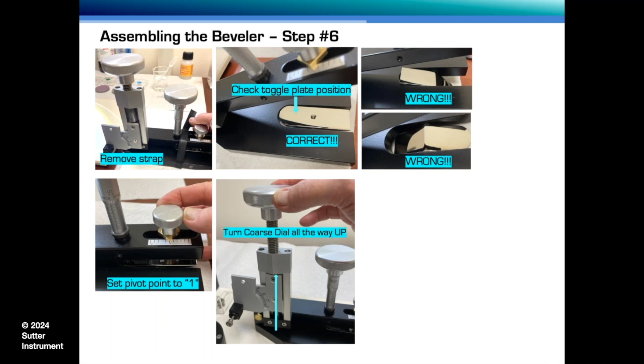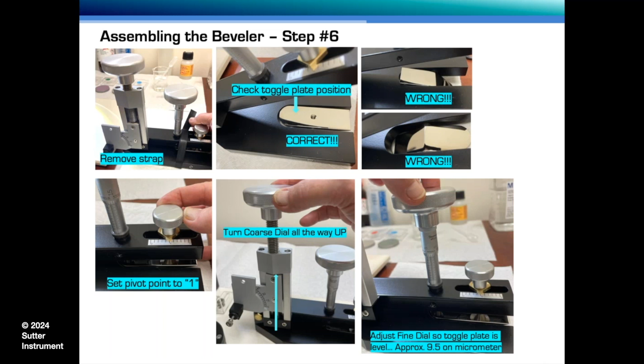You're going to dial the coarse knob all the way up, and you can see that the angle plate holder is almost flush with that top part of that assembly. And then you're going to dial the fine focus to around 9.5. That's where that toggle plate right there is level, and that's what you want. You want to make sure that you start with that every time you're starting to bevel a pipette. You want to re-level that with the fine dial.